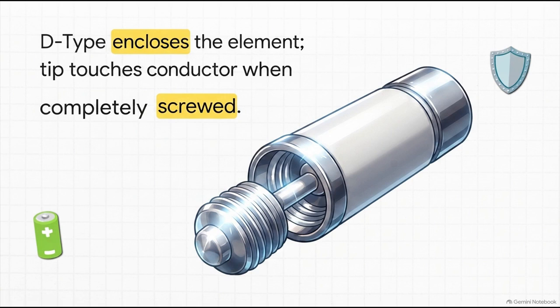Next, we have totally enclosed or cartridge fuses. It's exactly what it sounds like. The fuse element is totally sealed up inside a container with metal contacts on both sides. A classic example is the D-type cartridge fuse. And this is just a beautiful illustration of safe mechanical engineering. The cartridge is kept inside a fuse cap, and the tip of that cartridge literally only touches the conductor to complete the circuit when it is completely screwed into the adapter base. You can't accidentally shock yourself on it.